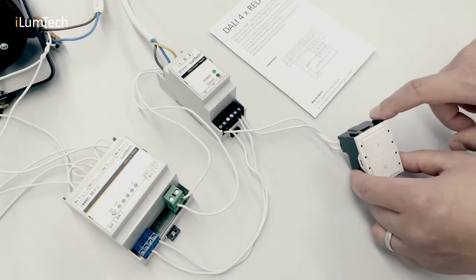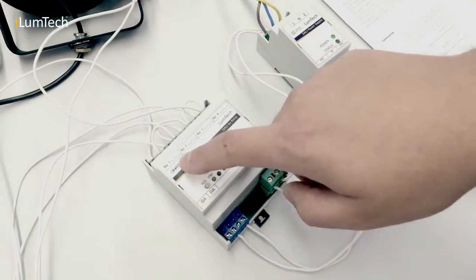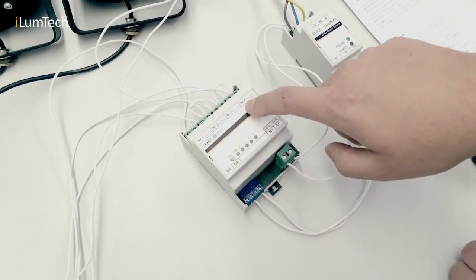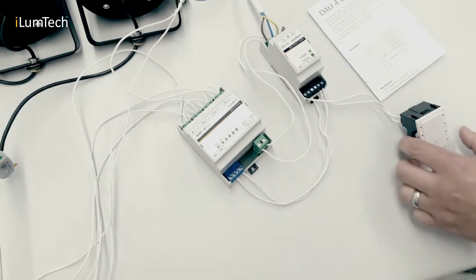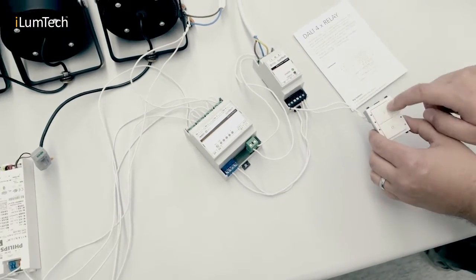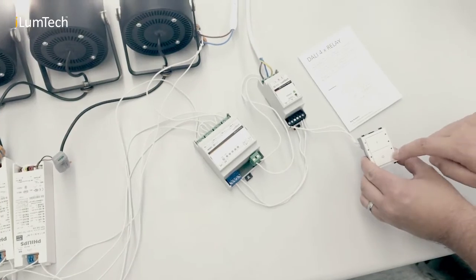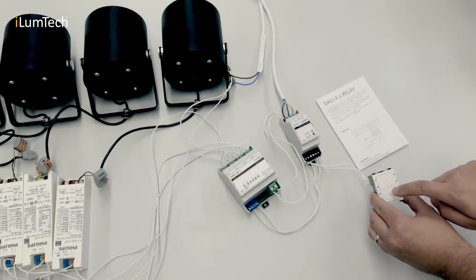After commissioning, you will see four new addresses on the DALI line with each address representing one relay contact. To change the state of the contacts, you can use direct level commands or standard commands such as OFF, RECALL MAX or RECALL SCENE.